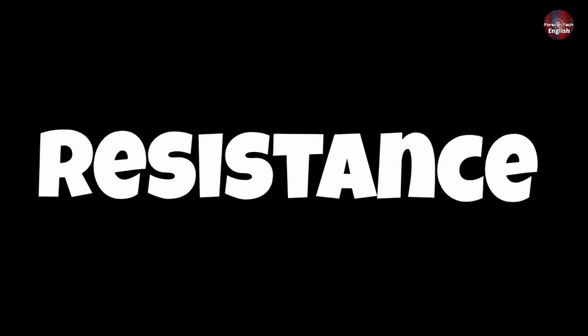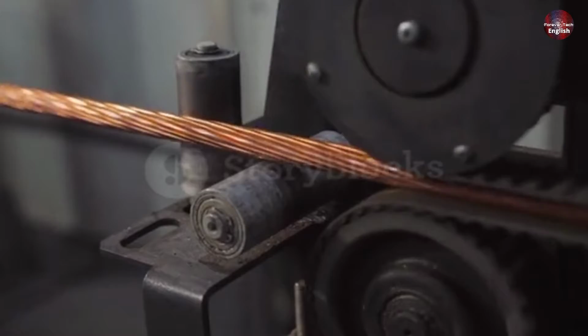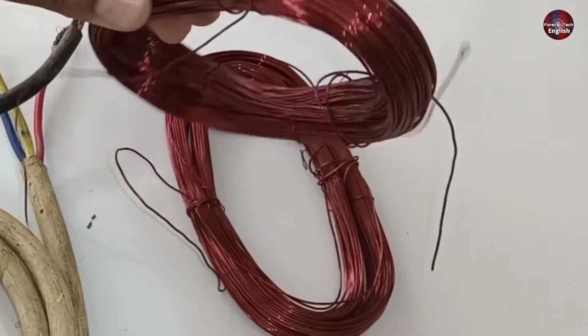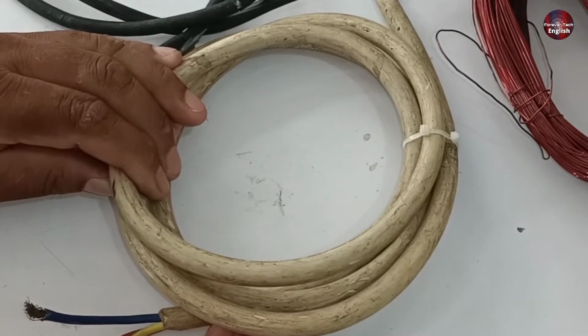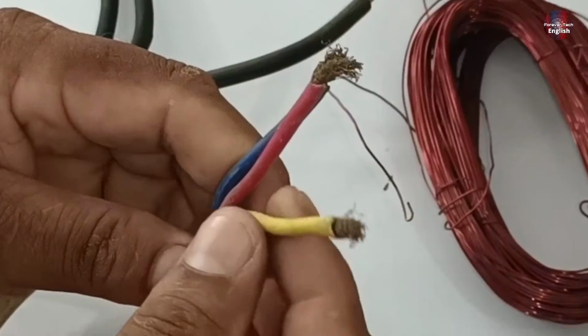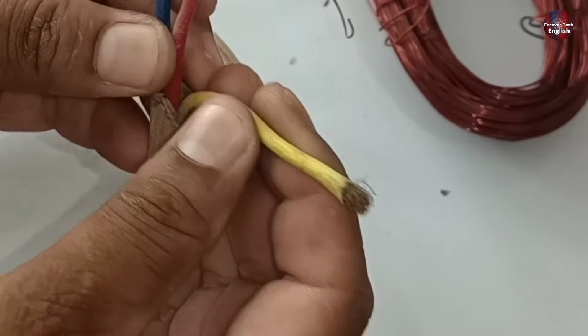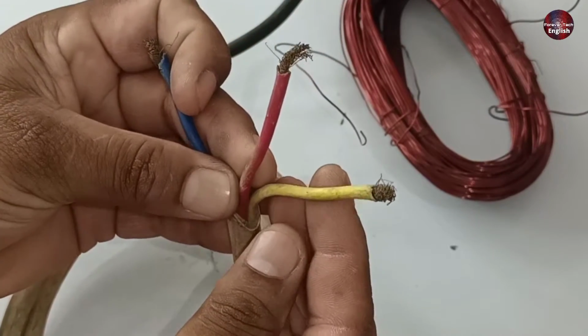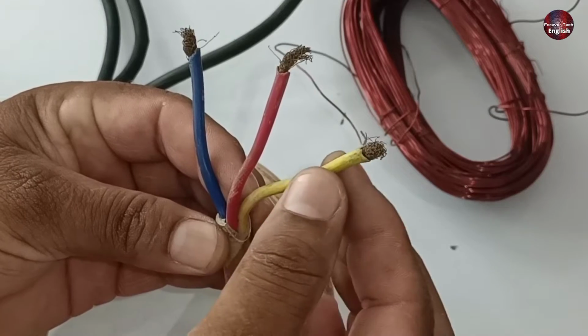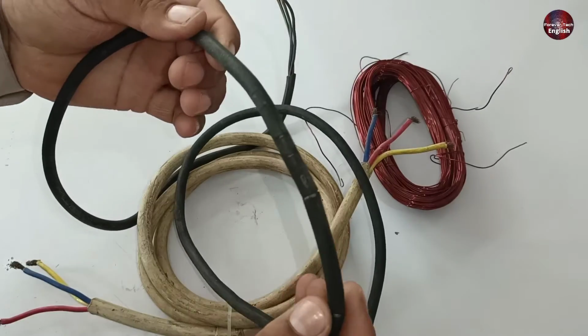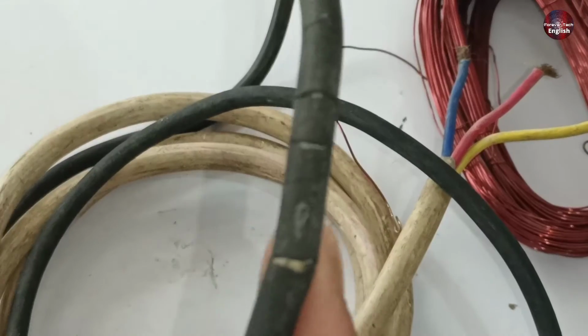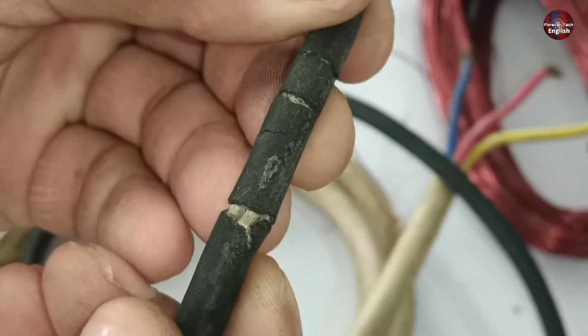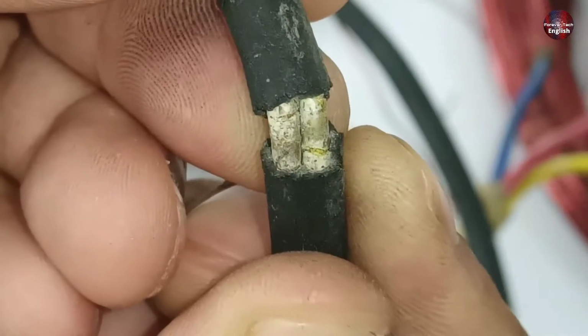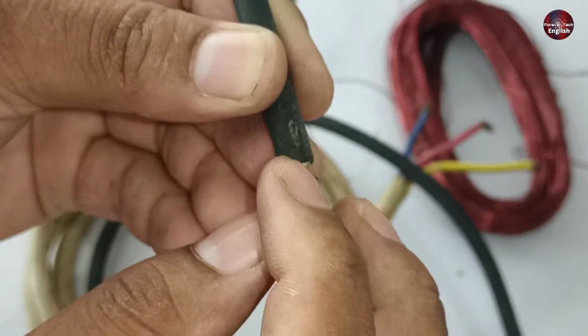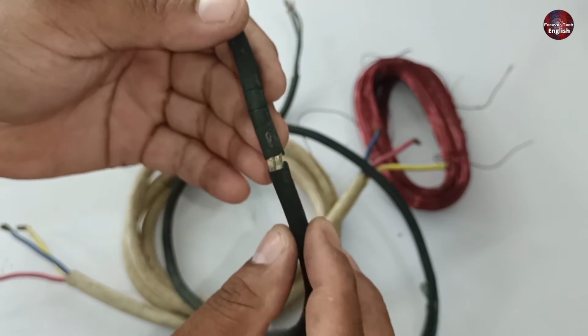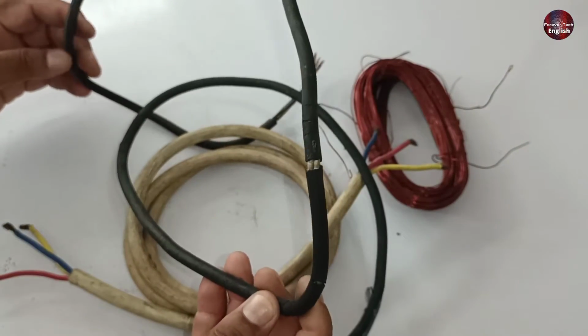Now, what is insulation resistance testing? Whenever wires are manufactured, they are made this way, as I have made coils from these wires, or they are made this way. So how will we test it? These wires have insulation on top of them to protect one wire from being attached to the other and prevent short circuits. We check whether the insulation has resistance between them or not. Because as time passes and for many other reasons, this wire, due to different weather conditions, its insulation is torn up. And also, the insulation inside the wire has cracked, which makes a short circuit. So this is what we check, whether these wires have a maximum resistance between the insulation of the wire.